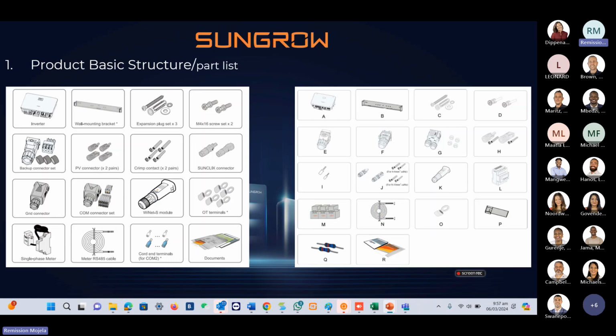So this is basically the product structure and part list. When you purchase one of our hybrid inverters, you basically get everything that you need to do the installation besides the cables and the breakers for your loads and the breakers that will supply the inverter itself. All the other devices will be inside the box for both the single phase and the three-phase hybrid inverters. The part list that I'm currently highlighting is the single phase part list, and the other one is the three-phase part list.